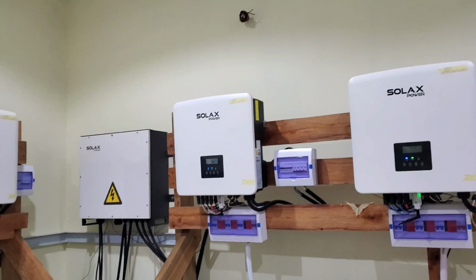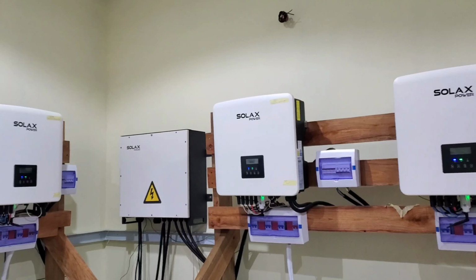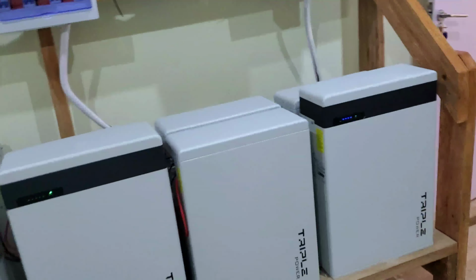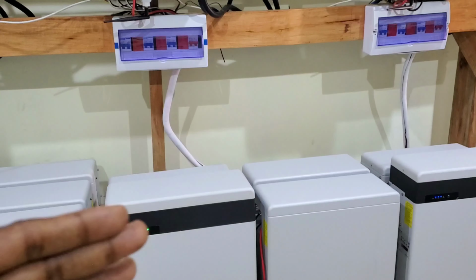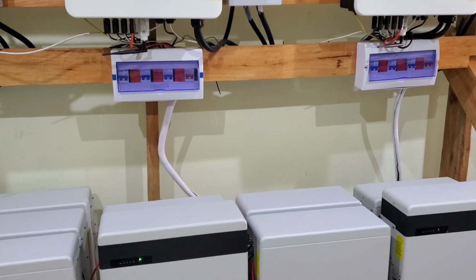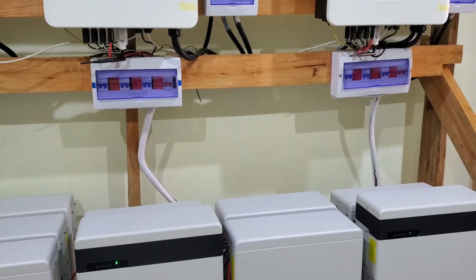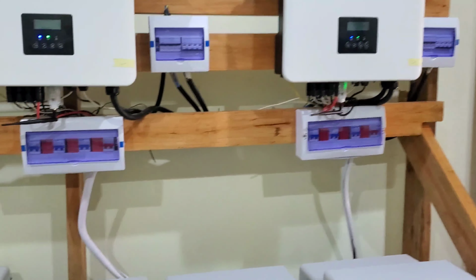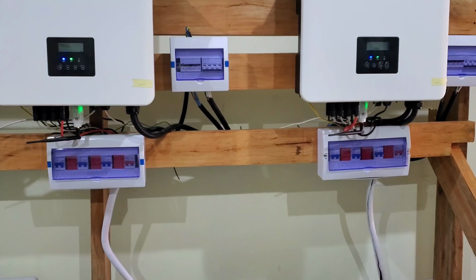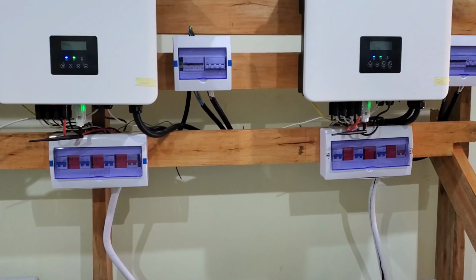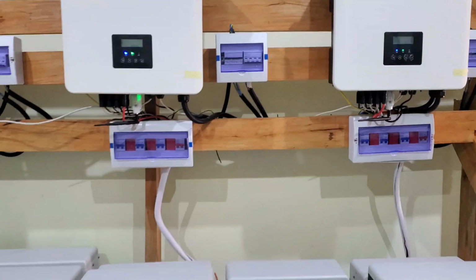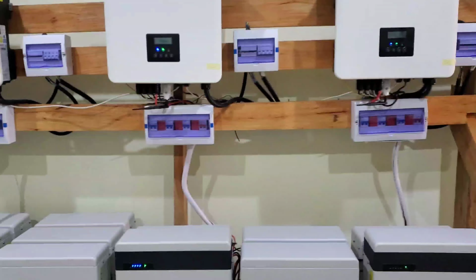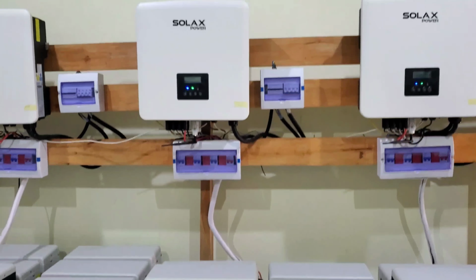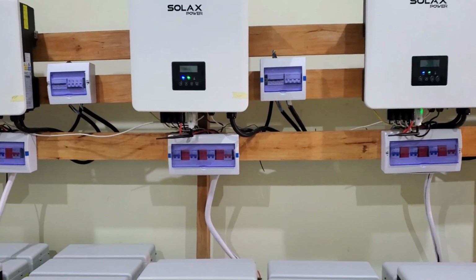So how does it compare? If you recall, when we turned the system on at the other site, we ran into some issues. We had battery cables. First of all, the initial issue was we couldn't get the battery to communicate with the inverter. Remember, we had 24 or 25 Pylontech batteries, and in order for them to communicate we needed a hub. The hub would not communicate with the inverter. That was the first one.